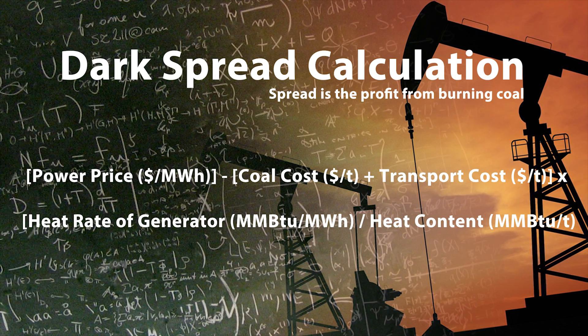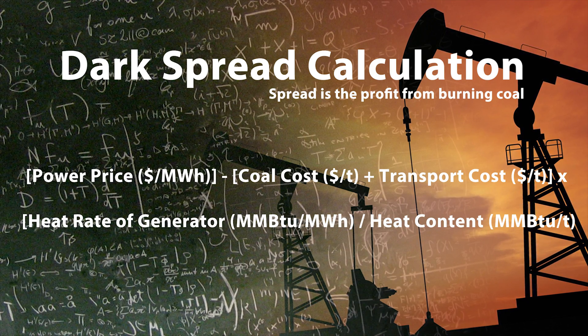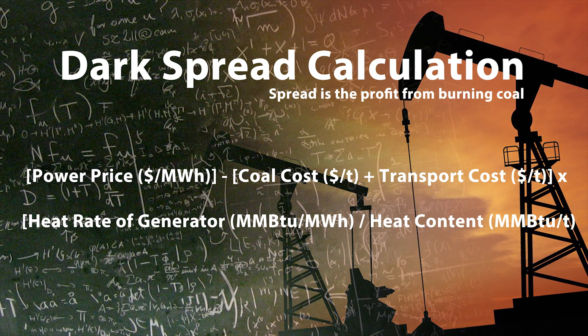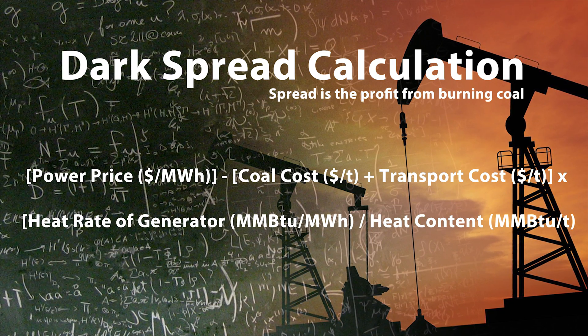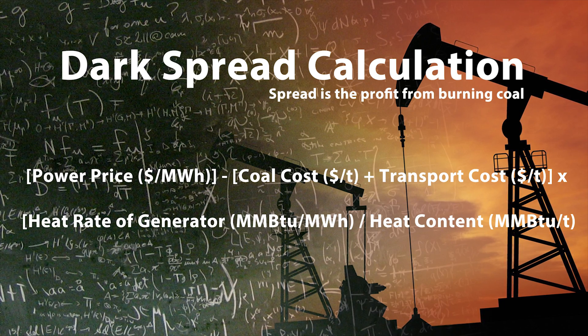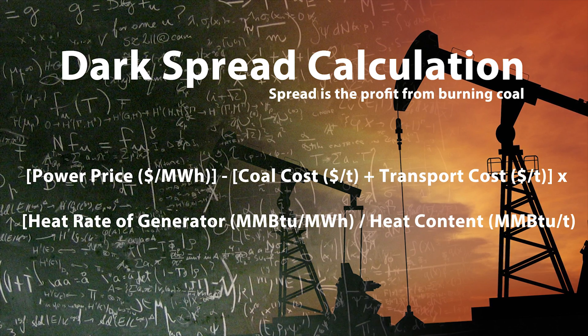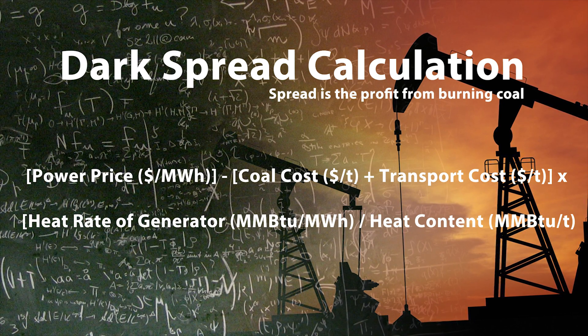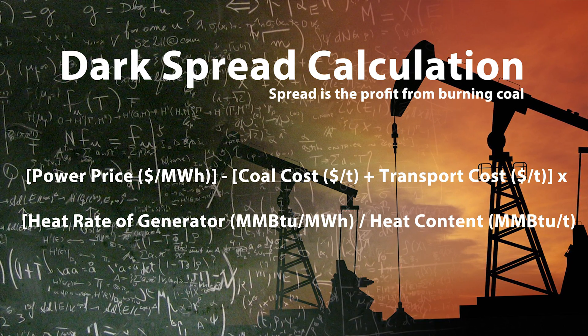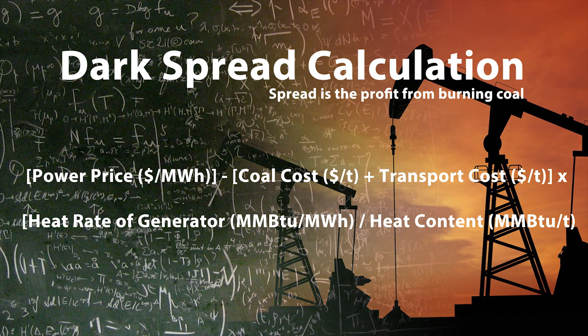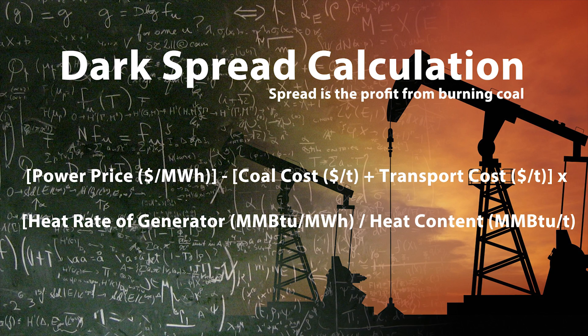The next two terms — the heat rate and the heat content — are functions of the physical nature of the process. Fundamentally what we're doing is taking the energy that's in the coal, burning it and converting it into electricity. Therefore we need a function that accounts for the amount of energy within the fuel — that's the heat content — and also how efficient we are at extracting that heat, which is the heat rate, measuring the efficiency of the unit. Once you combine these terms, we have the power price as revenue, the coal and transportation cost, and the conversion factor, which is effectively the heat rate and the heat content.